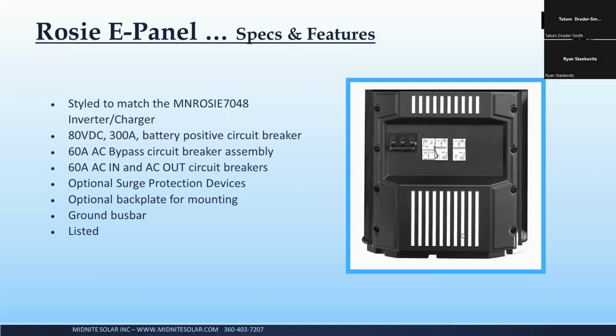You got a 60 amp bypass, 60 amp input, 60 amp output breakers, connections via surge protection. There is an optional back plate, and you do have your 300 amp battery breaker there to go with it. We are working right now today on the follower E panels to allow you to stack two. And then we're going to be working on a 120 amp primary E panel for a stacked pair. Because remember, the Rosie has a 60 amp internal bypass. So if you had two Rosies, you could theoretically pass through 100 amps to back up a 100 amp load center in a residence.